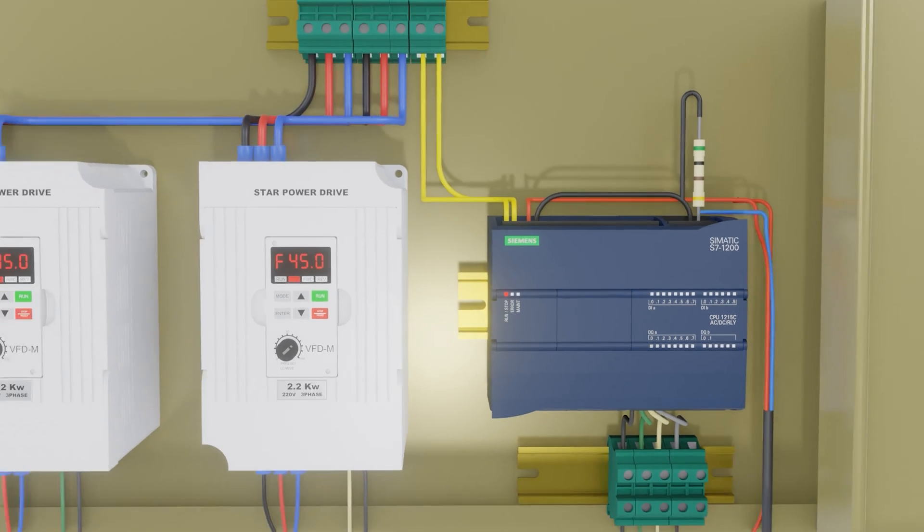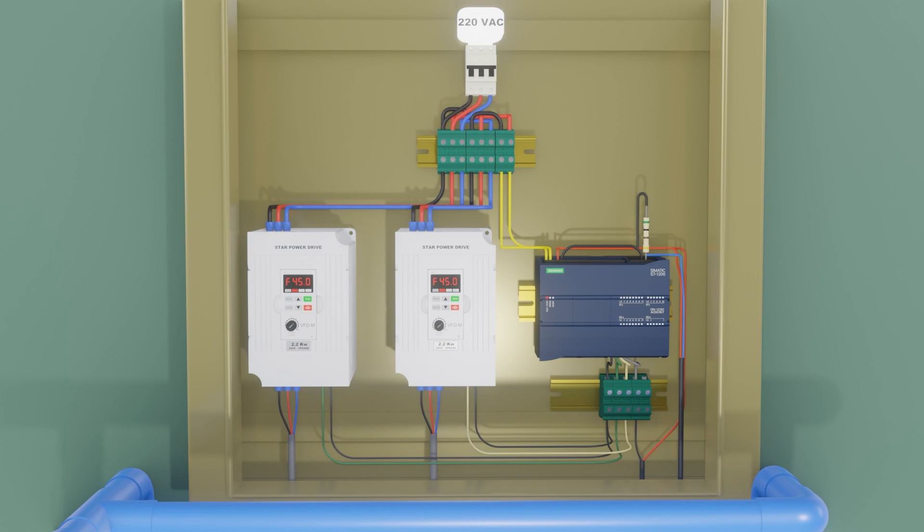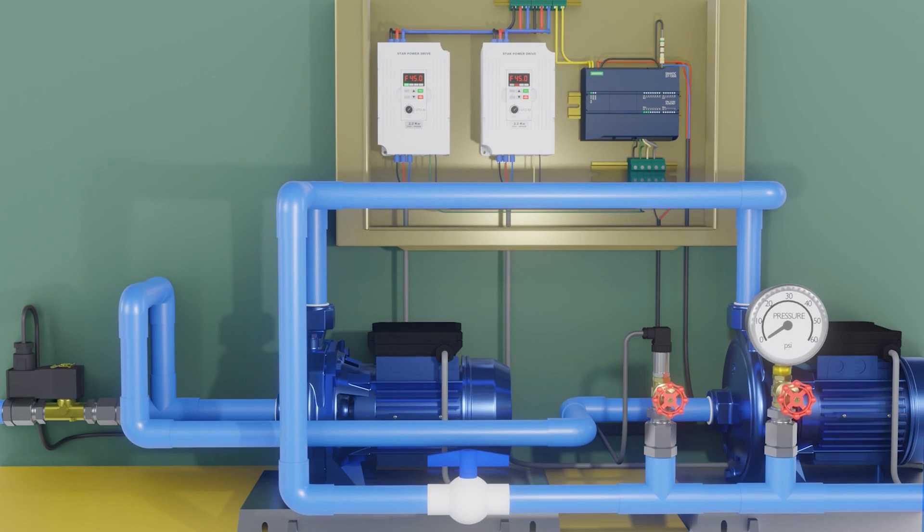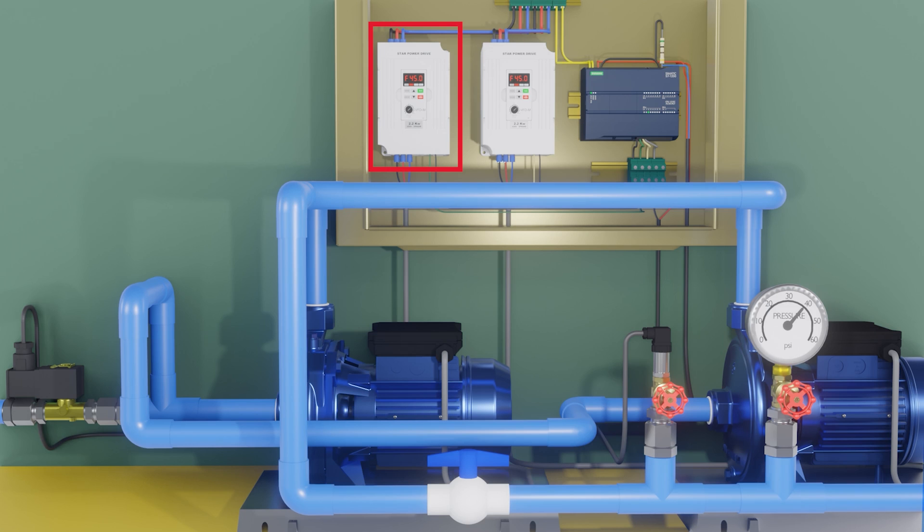The PLC is in stop, I will put it in run. Turn on output Q0.2 and Q0.0. We see that the pressure begins to rise to 40 PSI. And frequency drive 1 turns off.